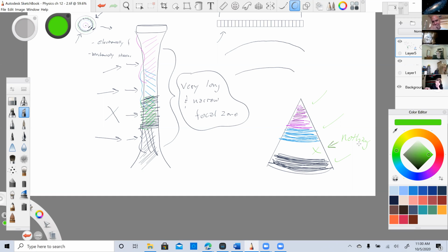Redirection of sound beams, that's what he's asking about there, is steering. These can only be mechanically steered. They cannot steer electronically. Focusing, that's done electronically because we can focus using different elements. Each one has its own focal point.